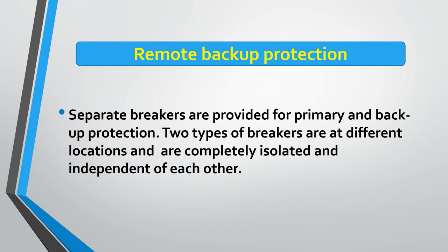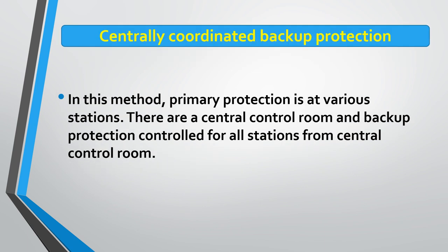In remote backup protection, separate breakers are provided for primary and backup protection. The two types of breakers are at different locations and are completely isolated and independent of each other — if one element fails, the second comes into picture. In addition, there is centrally coordinated backup protection, where primary protection is at various stations and backup protection for all stations is controlled from a central control room.